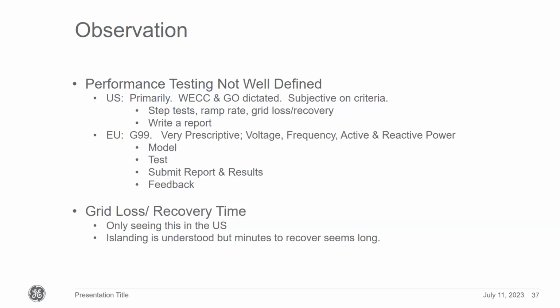Right now it's pretty much the WECC document, and grid operators dictate it, with somewhat subjective criteria. The WECC document basically says match the model, but doesn't say how well. It doesn't give criteria on settling time, response times, the typical CTQs, critical-to-quality aspects we've been looking at. The tests are pretty quick, generally some step tests, ramp rates, grid loss recovery. We write a report, submit it, and never hear about it again.